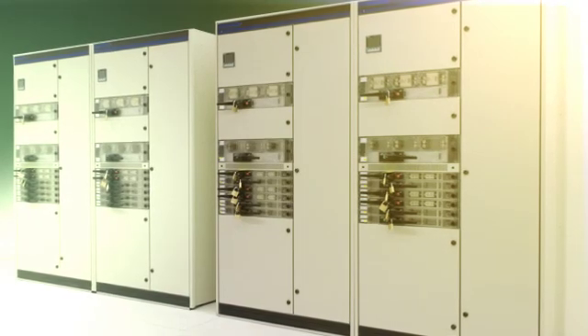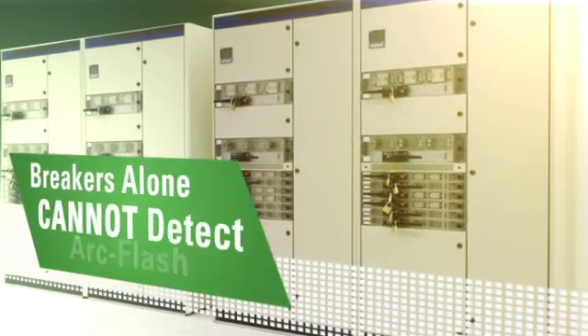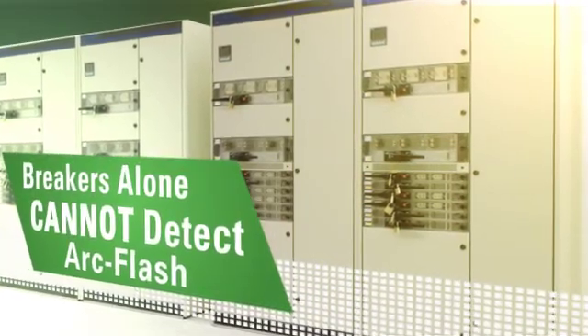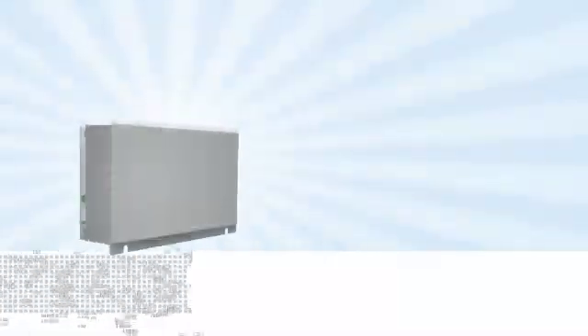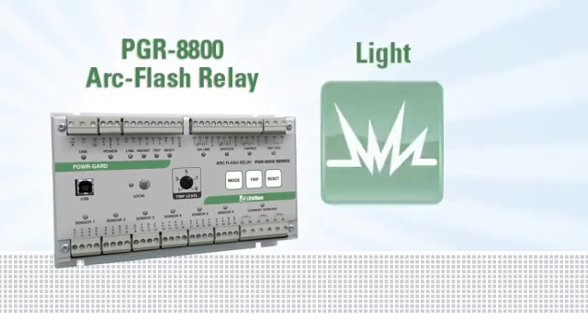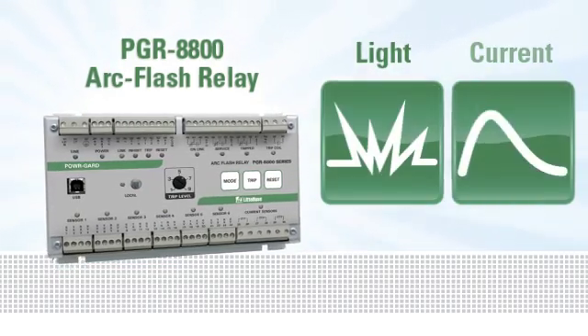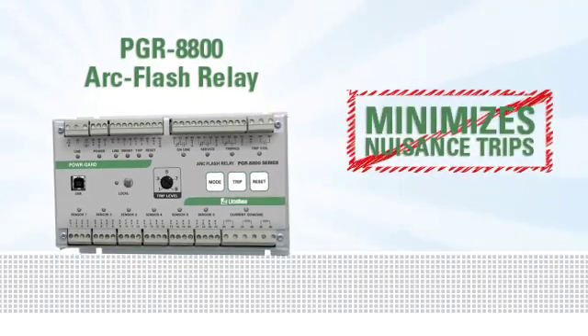Because the early stages of an arc flash draw a fraction of bolted fault current, circuit breakers alone cannot distinguish between the arcing current and a typical inrush current. The PGR-8800 solves this problem by detecting both light and current. It provides superior arc flash protection while minimizing nuisance trips.